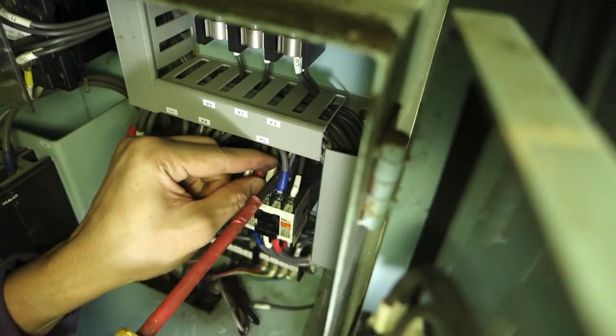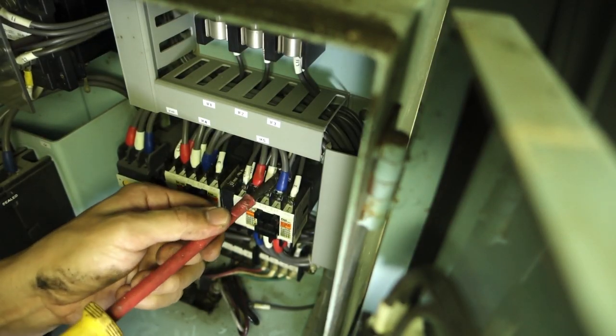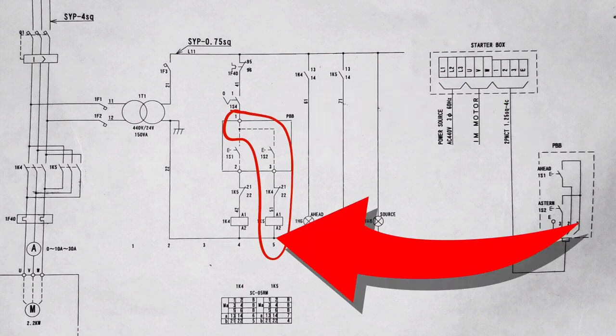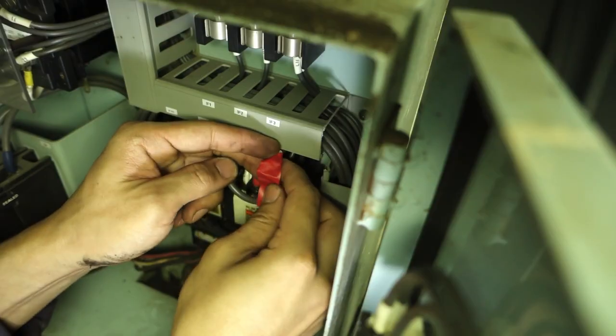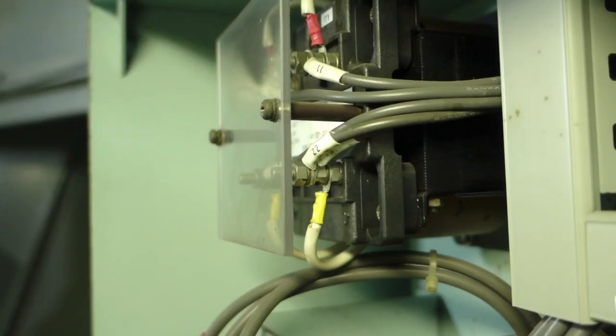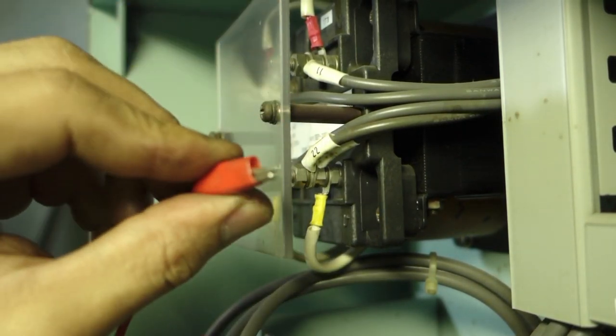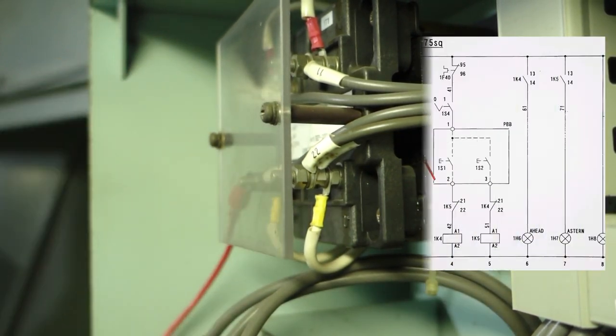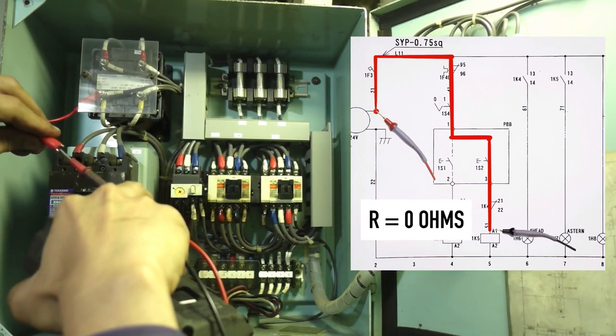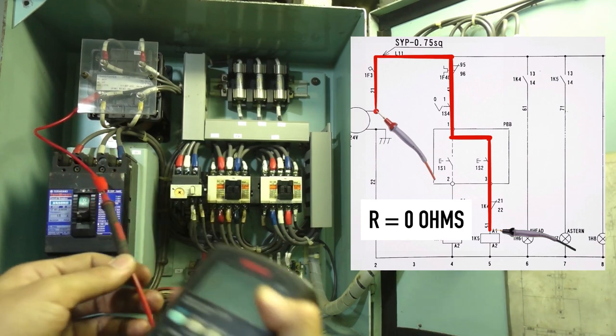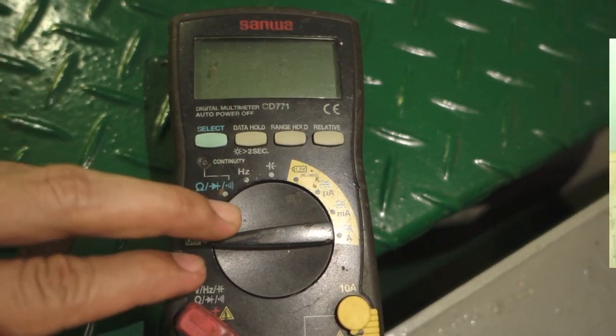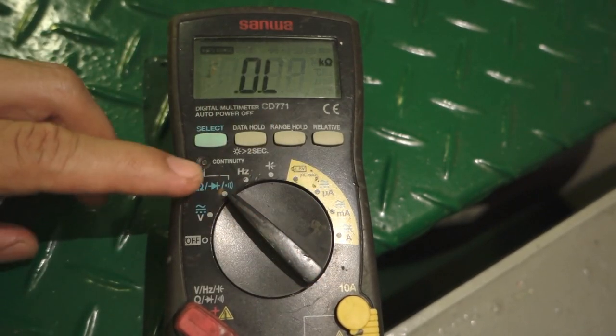Now that I have confirmed that there's no more voltage in the system, my next goal is to isolate the circuit I will be testing, disconnecting at this one of the terminal of this circuit. I prefer to disconnect the terminal after the load. I used an alligator clip to connect one of my leads right after the control source voltage. In this setup I expect a continuity reading before the load and higher resistance reading. Now I can start my testing and I will see you in a bit.